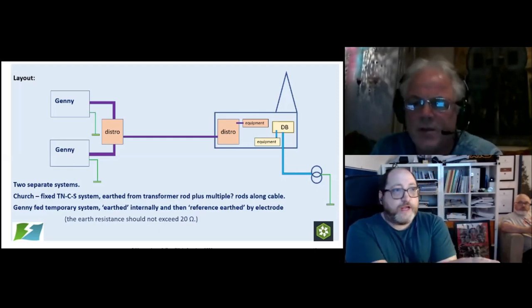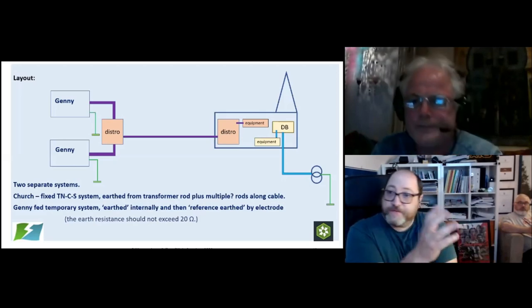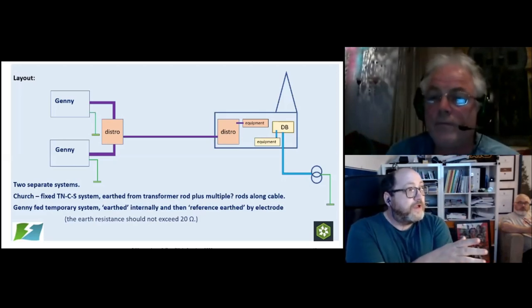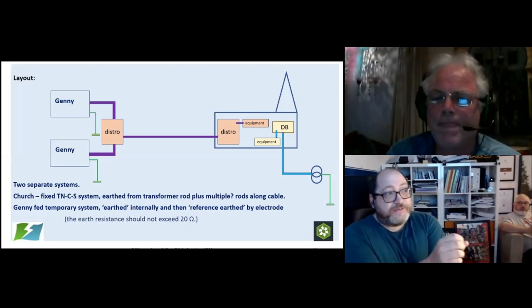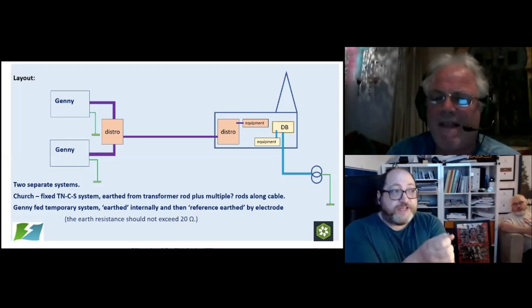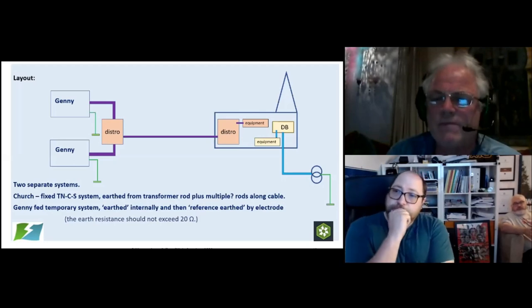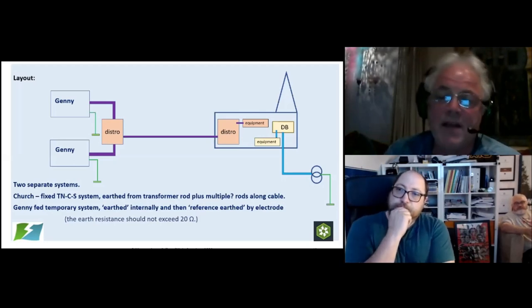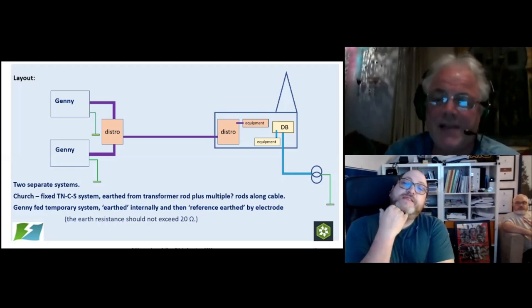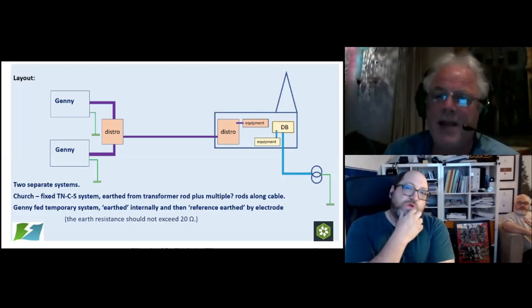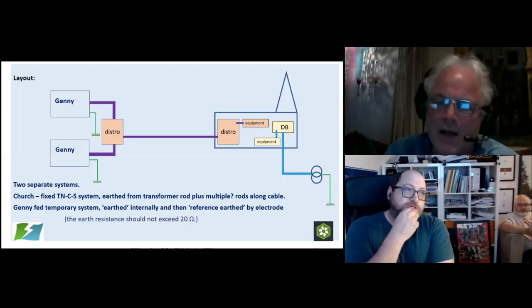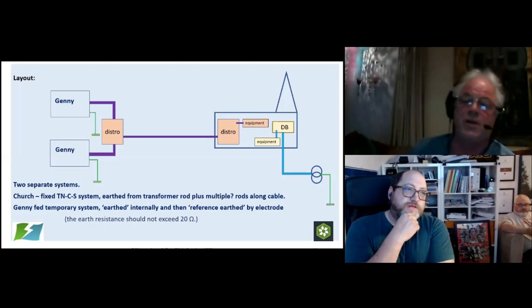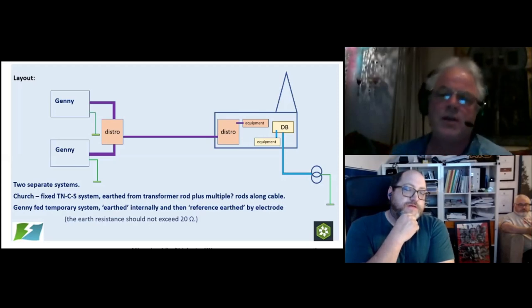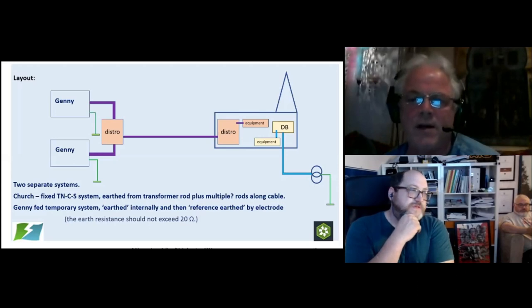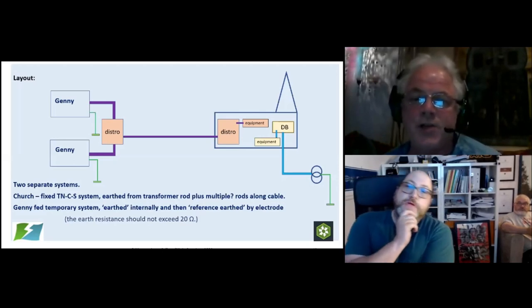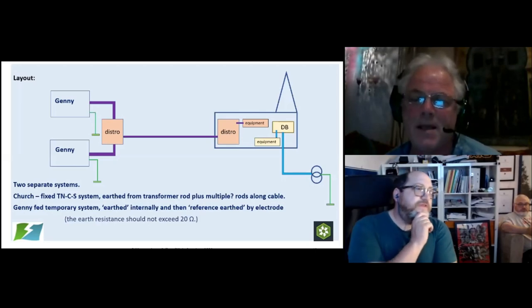I'm just looking in the chat, and then I'm going to pop over to some of the questions. There's mention of SPDs and lightning. So John O'Neill asks: if connected to the MET and there's lightning protection on the church, are the generators going to therefore need surge protection? If they're connected together, there is an issue there. In the unlikely event of a lightning strike, if you have connected to the electrical or the earthing system of the fixed installation, then you would probably need surge protection on your supply.